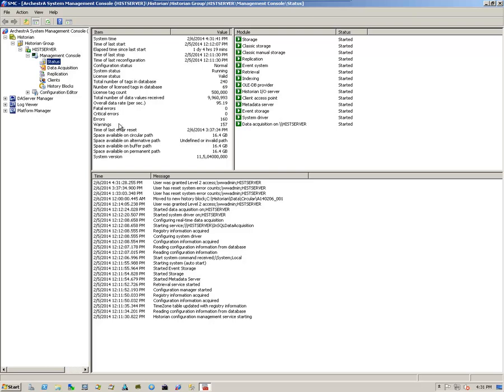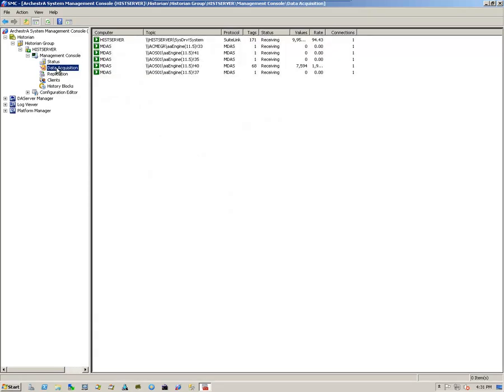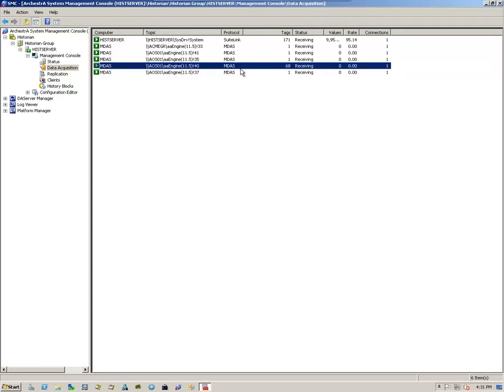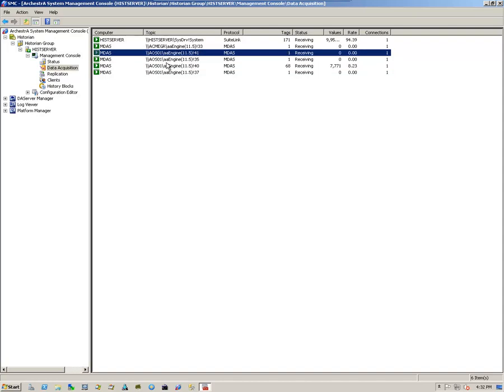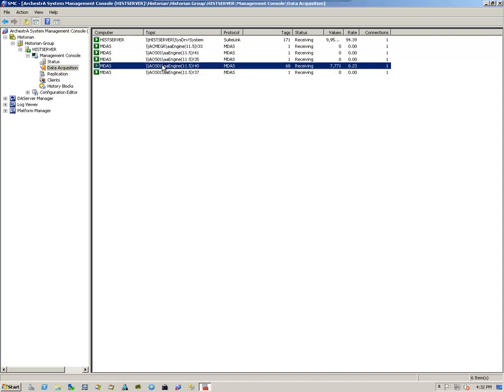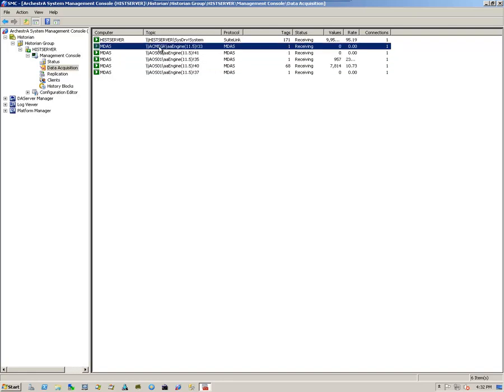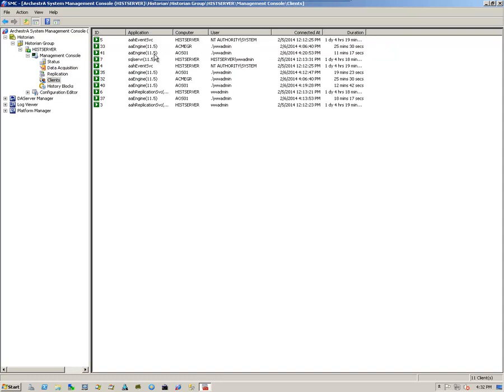And I'm checking to make sure I have all of my modules online. And I see some errors and warnings here, but more than likely they're when I was deploying and redeploying the galaxy. But here is where I'm going to take a look and make sure that I have data coming into my historian. So I see all of this information coming from my object servers. And I have one engine coming from the galaxy itself. I see clients are connected. All greens.